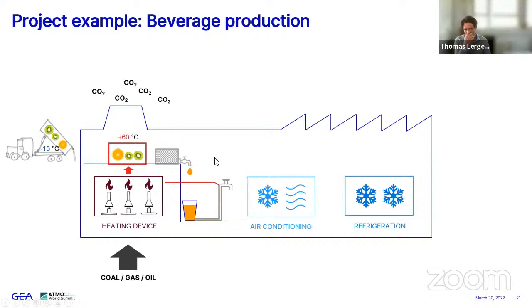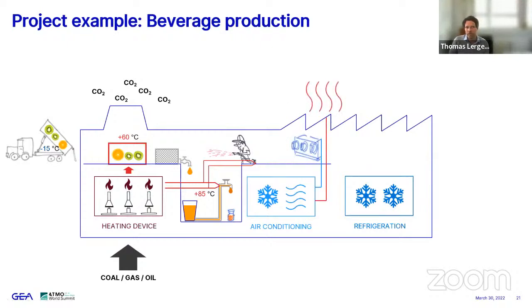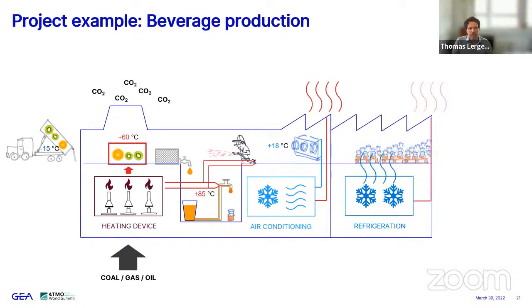And the second heating demand they have is for the cooking or the mixing of the juices, and they have hot cleaning water, so they need plus 85 degrees Celsius on their heating or cooking lines and for the heating water. Then room climatization, so plus 16 to plus 18 degrees Celsius, air conditioning devices. And then the filled product: they're filling the smoothies into the bottles and storing it, so they have a storage room attached to the factory. This is running at very low plus degrees, like in your fridge, plus 4 degrees Celsius, for example. So this is how it looked in the past.